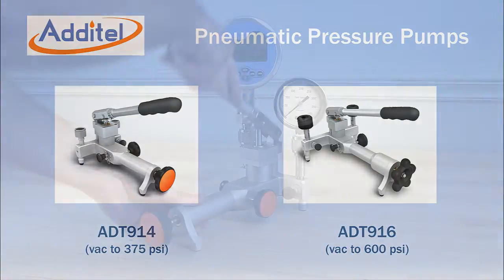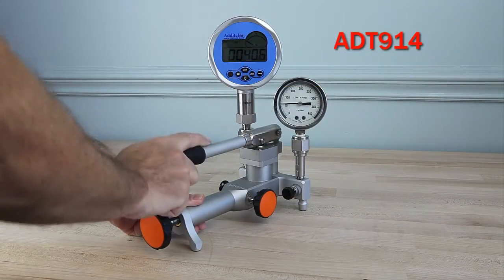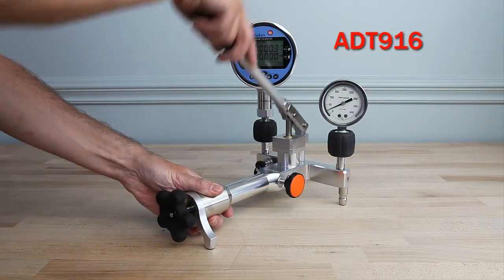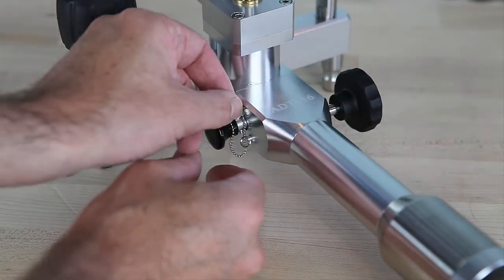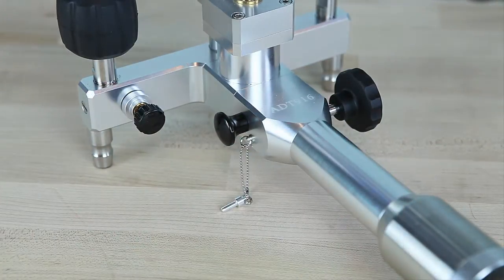The Additel ADT914 and 916 are pneumatic pressure pumps with maximum ranges of 375 PSI and 600 PSI respectively. Both pumps can also generate minus 14 PSI of vacuum by removing the pin from the vacuum pressure selection knob and pushing it in to select vacuum mode.